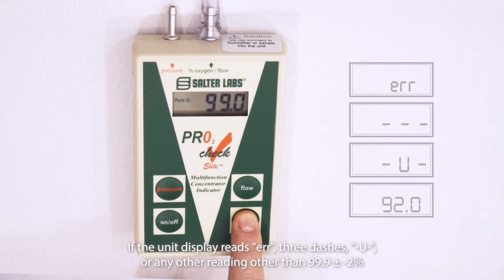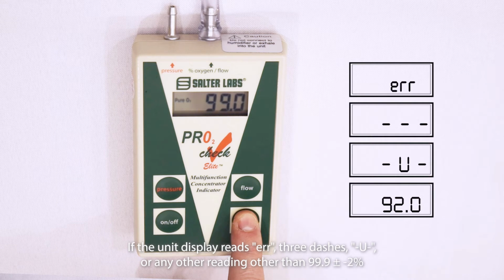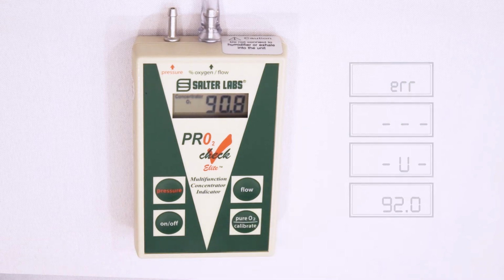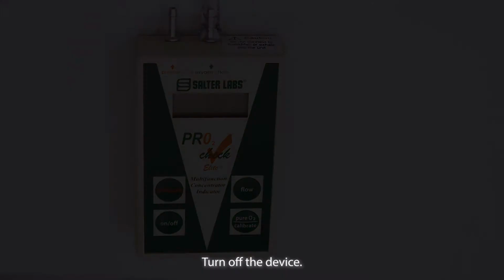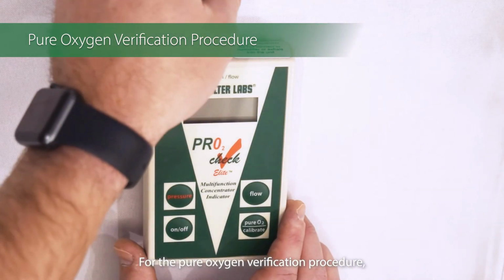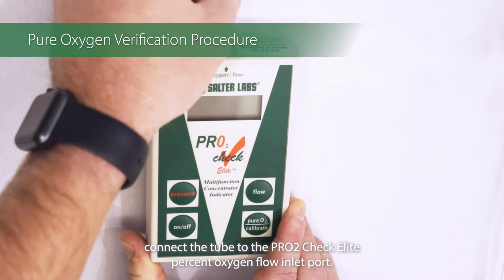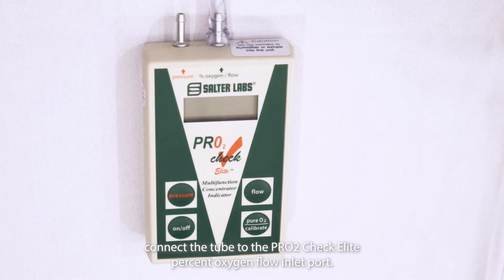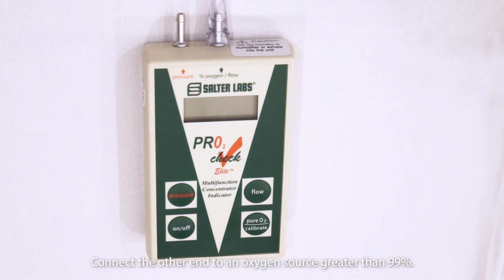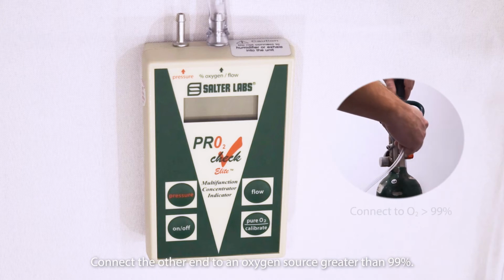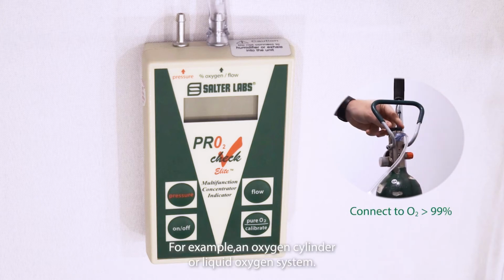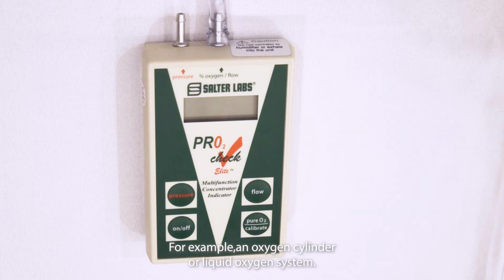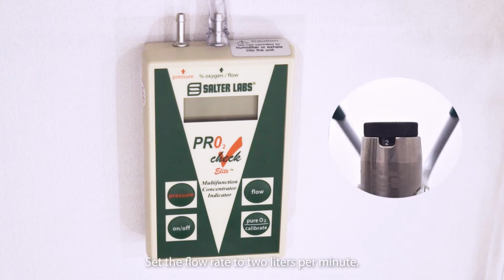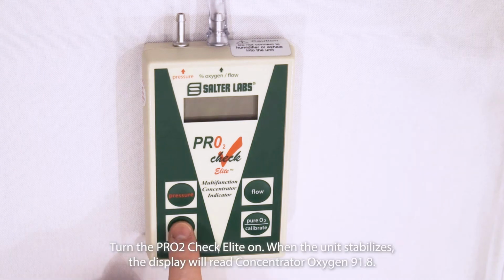If the unit display reads err, 3 dashes, U, or any other reading other than 99.9 plus or minus 2%, the source gas may not be pure oxygen. Turn off the device. For the pure oxygen verification procedure, connect the tube to the PRO2 Check Elite % oxygen flow inlet port. Connect the other end to an oxygen source greater than 99%, for example, an oxygen cylinder or liquid oxygen system. Set the flow rate to 2 liters per minute. Turn the PRO2 Check Elite on.